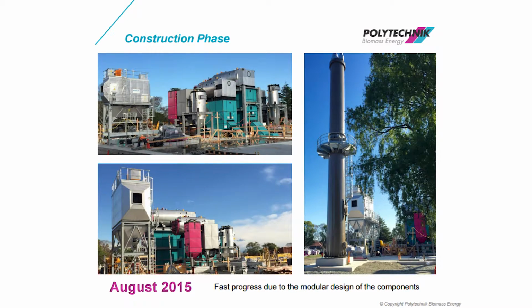This is the electrostatic precipitator that cleans up the flue gas. You can see the boilers are going here, the 4 meg, the 2 meg, and then this is a flue gas economizer, so that's used to recover waste heat from the exhaust gas and use it to preheat the incoming water into the boiler, just to maximise the efficiency. We have a multi-cyclone here, which helps to separate out any particulates, and then an air preheater here, which preheats the under-grate air going into the boiler, just assists with the drying of the fuel and combustion.